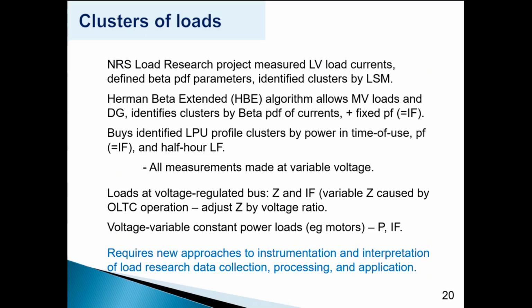Johannes or Lolo Base identified large power user profile customers by power in time of use. So the power at peak, standard, and off-peak times, the power factor or impedance factor, as I prefer to call it, and a half-hour load factor. And he was able to cluster the profiles then using these 5 parameters. And all of these measurements are made at variable voltage. When you talk about measuring the load, the power, the current, whatever it is, at the LV customer or the large power user, you don't have strict voltage control. So you're not really measuring the rated currents or rated power of those devices. And so we start looking at the probability density functions to look at the clusters.